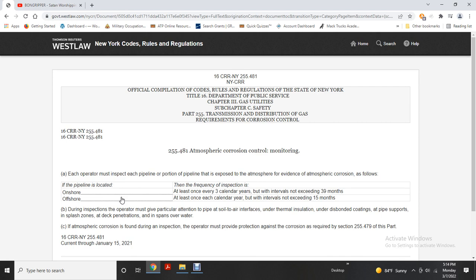Atmospheric corrosion control — inspection: each operator must inspect each portion of the pipeline exposed to the atmosphere for evidence of atmospheric corrosion. For onshore pipelines, inspection frequency must be at least once every three calendar years at intervals not exceeding 39 months. For offshore pipelines, inspection must occur at least once each calendar year at intervals not exceeding 15 months. During inspection, operators must give particular attention to the pipe-to-soil and air interface, under thermal insulation, under disbonded coatings, at pipe supports, splash zones, deck penetrations, and spans over water. Where atmospheric corrosion is found, protection must be provided as required by Section 255.479.